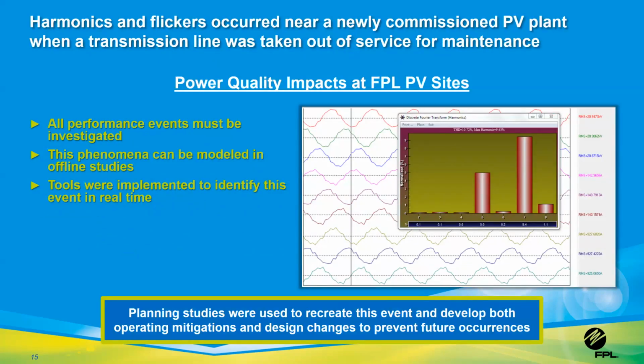So a few years ago, we commissioned a PV plant in a relatively weak area of our system. It worked well for a few months, and then when a nearby transmission line was taken out of service on a planned clearance, we started experiencing high harmonics and flicker. Through offline studies, we were able to recreate this phenomenon. We were able to recreate a resonant condition with elevated 5th and 7th harmonics. We worked with the vendor on plant setting changes to mitigate this issue. And we also performed studies to assess this risk at other IBR sites. We also required monitoring and alarming at future IBR sites, so going forward, we can detect this in real time immediately. Our offline studies led to a full understanding and comprehensive solution to this problem. Next slide, please.